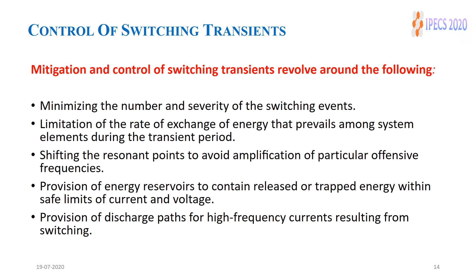The conclusion: the purpose of the study is to study the transients from utility capacitor bank switching in a real system. We studied harmonics and transient overvoltages for different switching times and different places, close to the load and close to the capacitor buses, low-level buses. In addition, we built a small-scale model in our laboratory test system. We observed different harmonic orders, and the 7th order harmonic is a little higher than the standard, so we have to take care when we design the power network. So this is our paper.